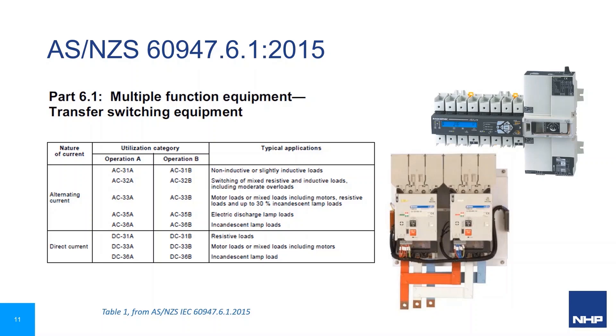Transfer switching equipment is defined in low voltage switchgear IEC 60947 part 6.1, with utilisation categories for changeover of different load types and function. Category A for frequent operation and Category B for infrequent or occasional switching is the same as part 3.